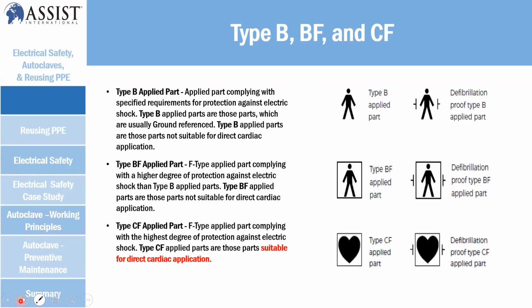Type B, BF, and CF are applied part types. You're going to see these symbols where you connect your ECG line, SpO2, NIBP, and so on. The type B symbol represents ground reference, like NIBP, and is not suitable for direct cardiac application. And type BF is an F-type applied part that has isolation and protects against electrical shock. So you can see type BF and type BF with defib proof.